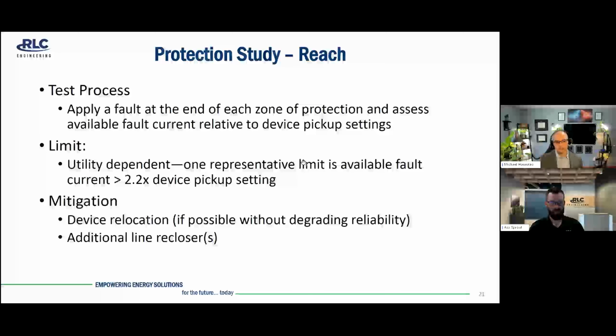Now for reach, what we typically see is the biggest impact to reach is if you had to go and adjust one of those minimum pickup settings. If you didn't have to adjust any of those minimum pickup settings, we tend to find that the impact to reach is pretty minimal. To look at this, we apply a fault at the end of each zone of protection and assess the available fault current relative to the device pickup settings.